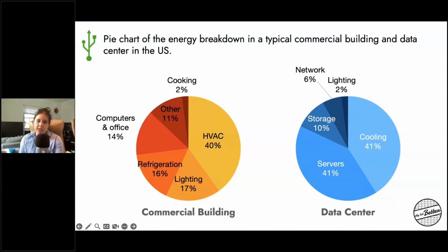For a data center, as you can imagine, the server load is big, but the cooling load is just as big for that space. To compare these two, take a look at lighting at only 2%, compared to the large load of servers and cooling. This doesn't mean to stop installing those LED lights — yes, we want to do that — however, don't expect lighting to really hold up your project for a data center. We really want to focus on cooling and the server load to make a big impact.